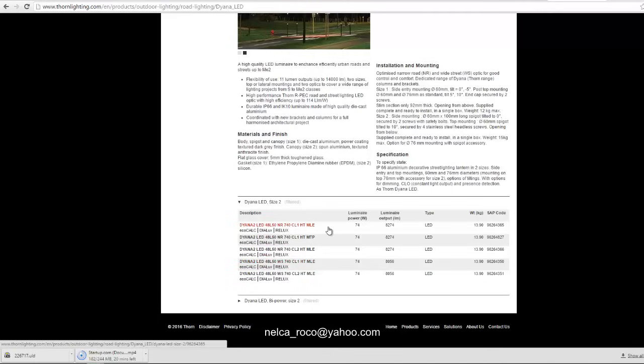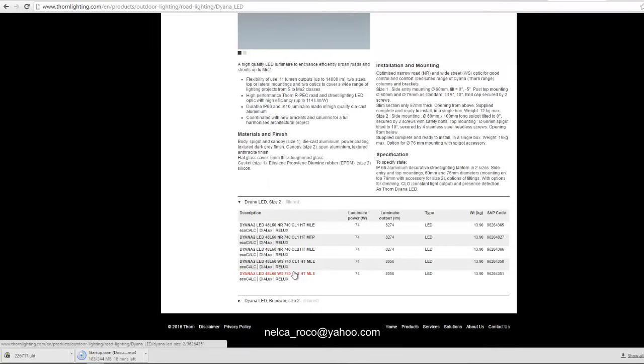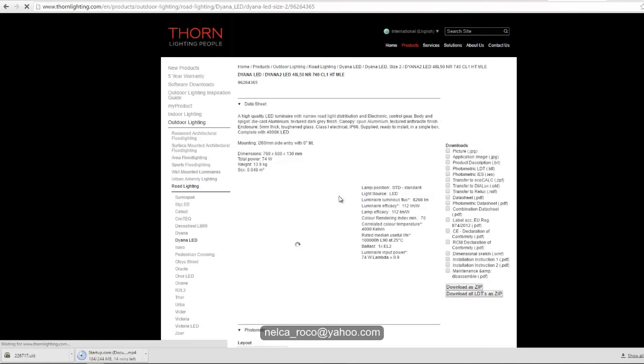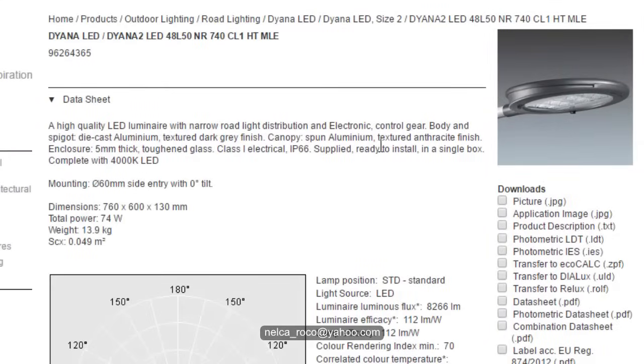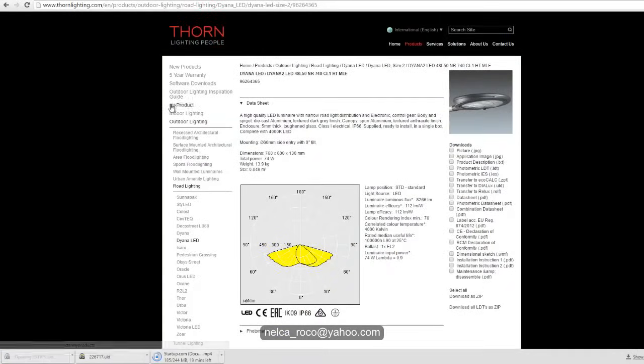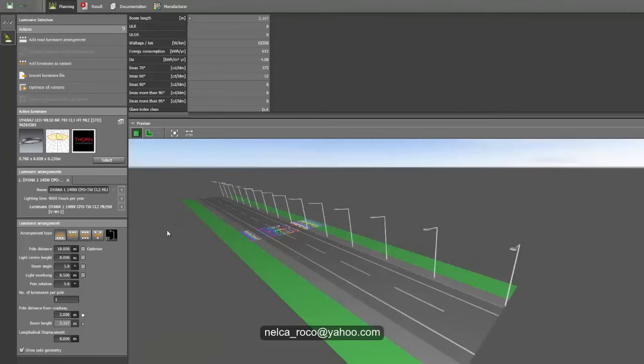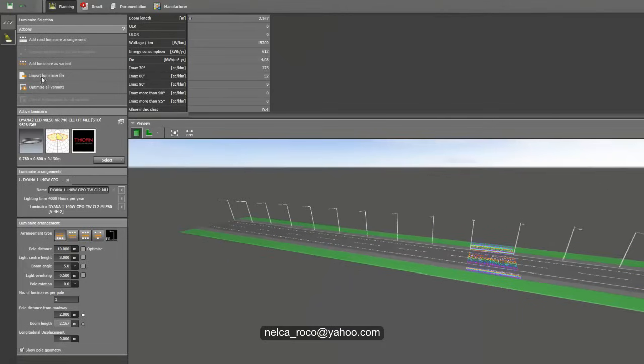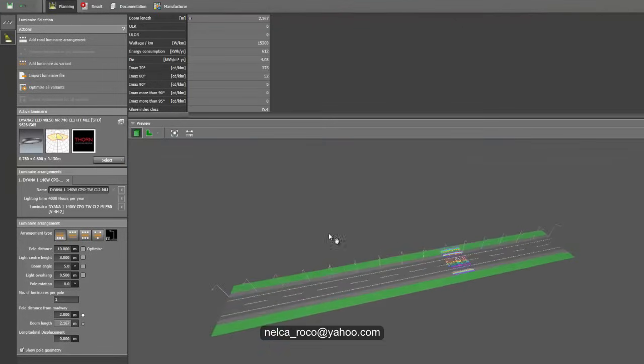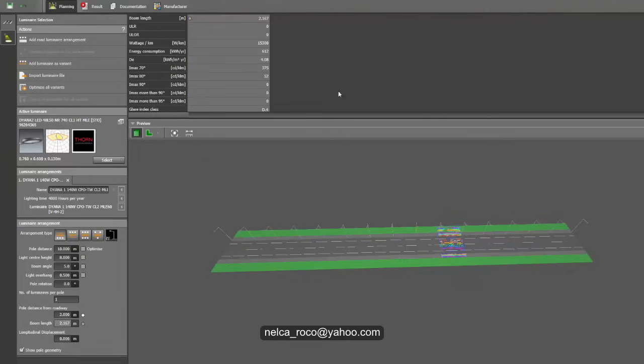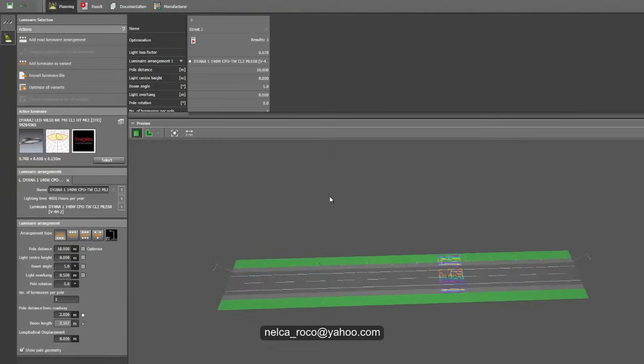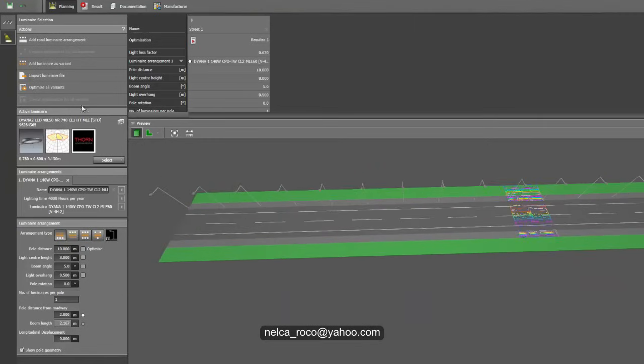Please ask the manufacturer or lighting supplier what the codes mean. Let's select this fitting: 'high quality LED with narrower lighting distribution.' I think this is the best choice because our road is narrow — only two lanes — so a narrow beam is ideal. Once selected, click the DIALux link, it will go to the download option. The file is now loaded in DIALux. The great thing about DIALux Evo is you can compare different fittings.